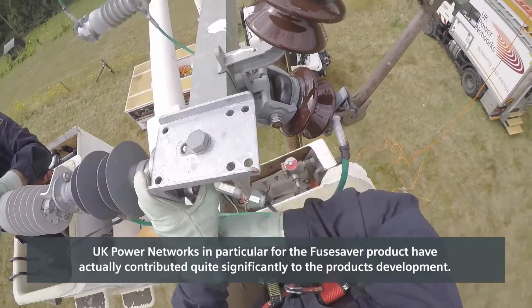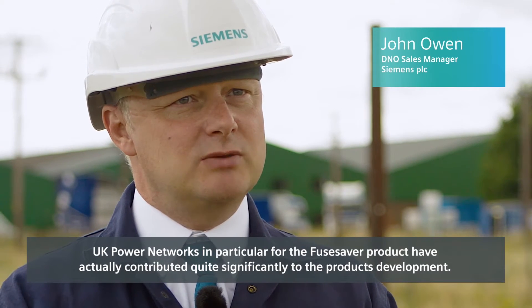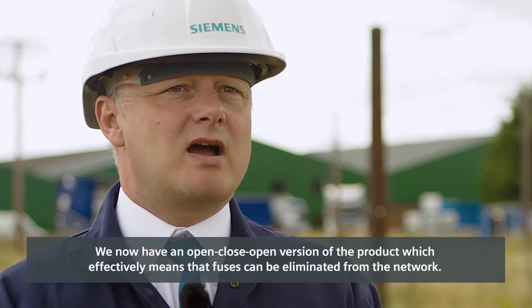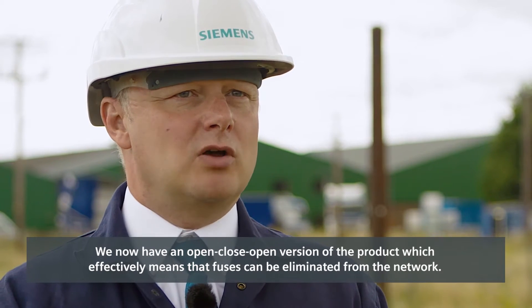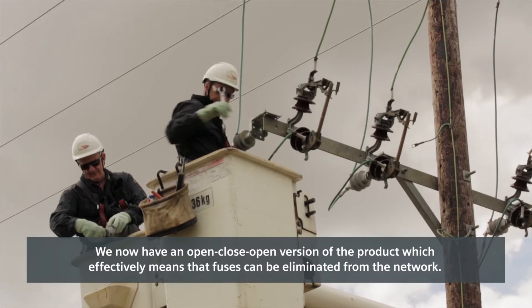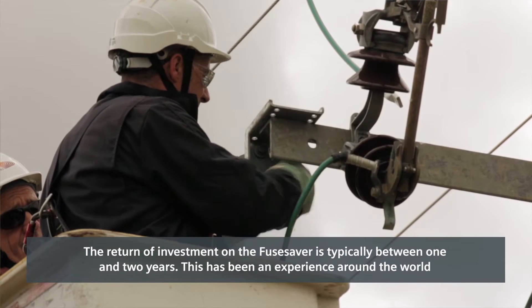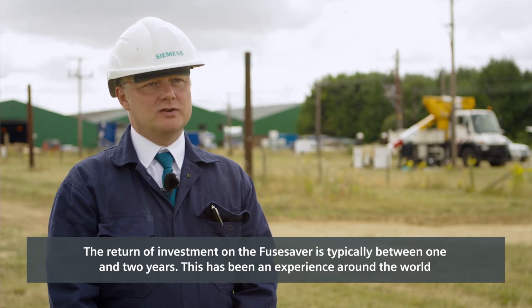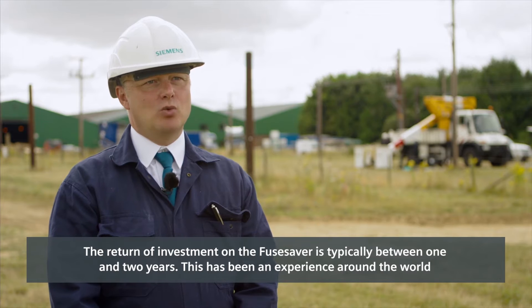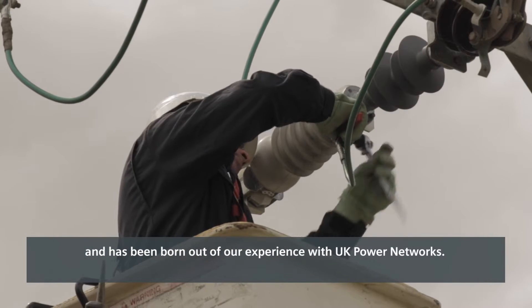UK Power Networks in particular has contributed quite significantly to the Fusesaver product's development. We now have an open-close-open version of the product, which effectively means that fuses can be eliminated from the network. Return on investment for the Fusesaver is typically between one and two years, and this has been borne out by our experience with UK Power Networks around the world.